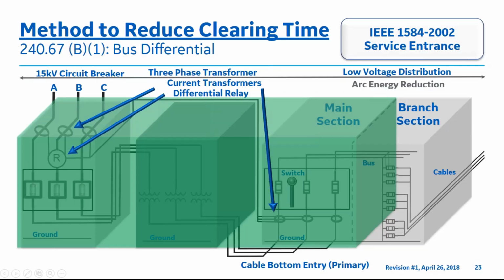If the CTs can be placed on the load side of the low voltage main fuse switch, which is just above the switch in this picture, it would provide the optimal zone of protection. Every part of the line side will have the high-speed protection of the transformer differential. The placement of the CTs connected to the protective relay in the low voltage fuse main section needs to be carefully considered to meet the 240.67 code requirement.